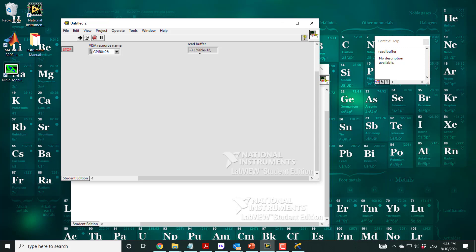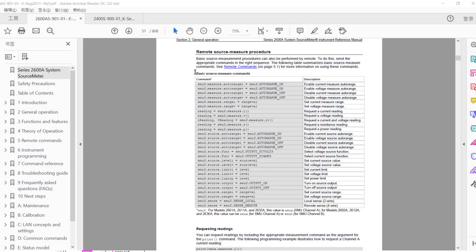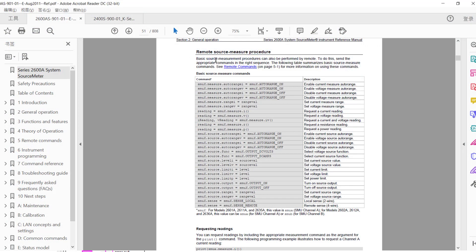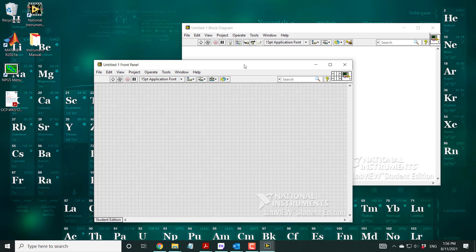Going back to the menus, there is a page on writing remote source measurement procedures with some basic and more advanced commands. These cover how to turn on the output, define the range, define what the measurement is — source current, voltage, or current and voltage simultaneously — and set the levels. All of these commands need to be sent via VISA Write to the system to start taking readings.